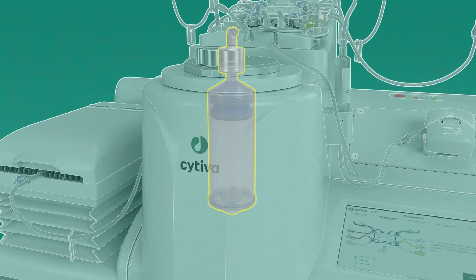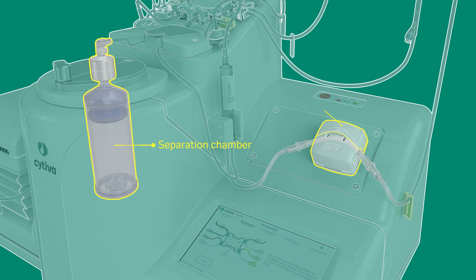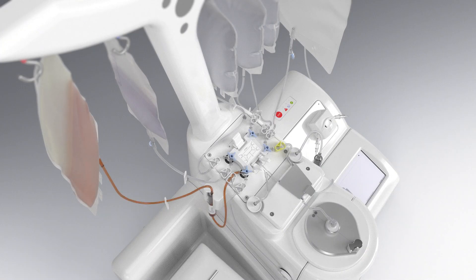The core technology of the Sepax instrument includes an electric centrifugation motor, pneumatic circuitry to drive the single-use kit separation chamber piston, and a peristaltic pump for filling, centrifugation, and extraction steps.